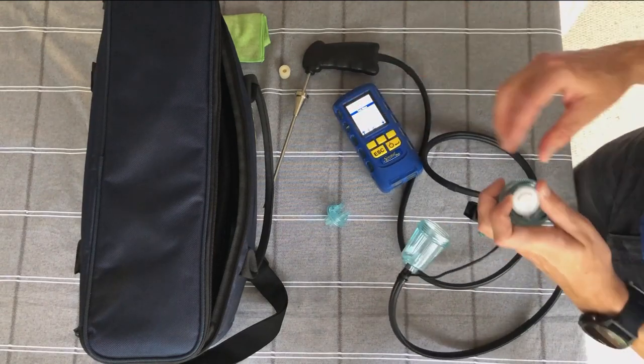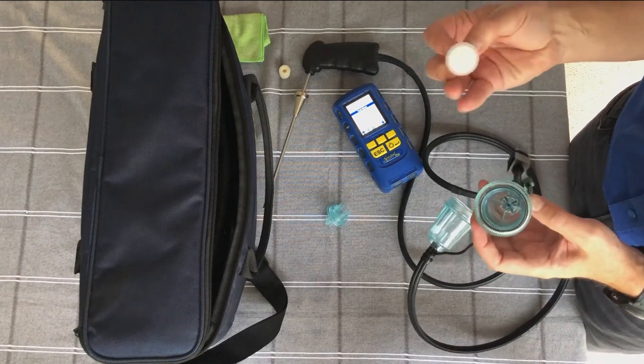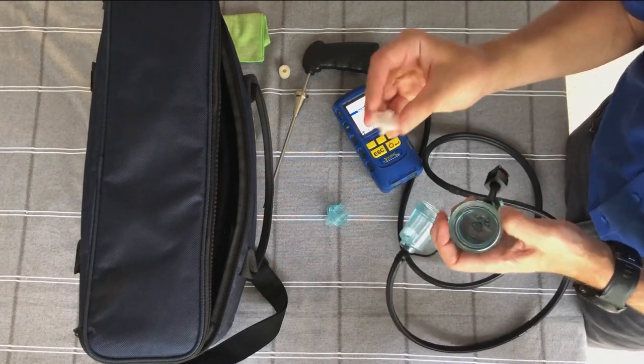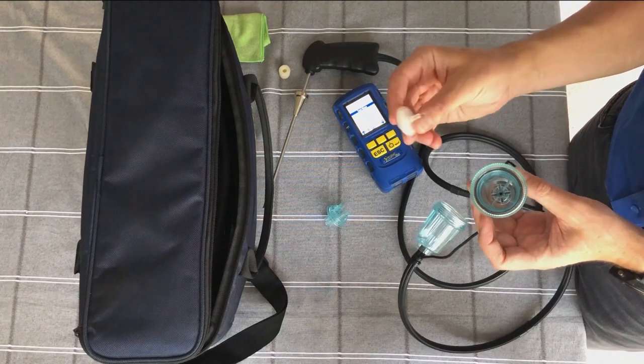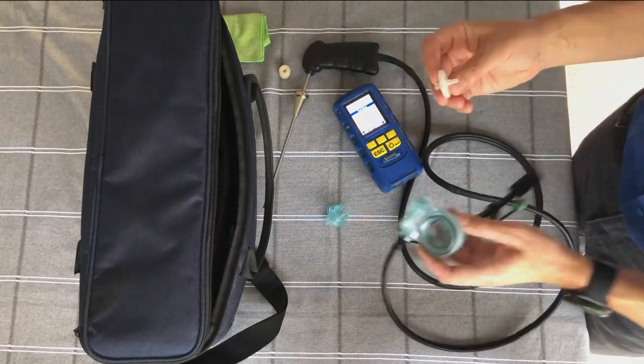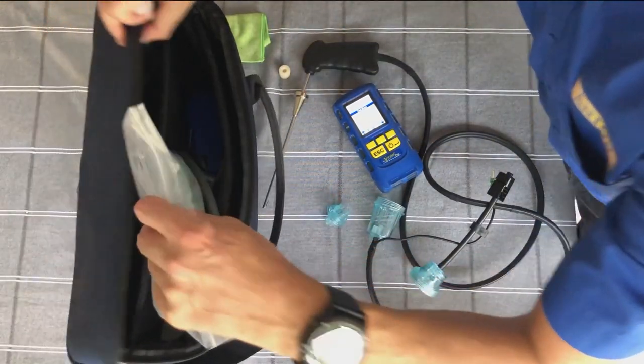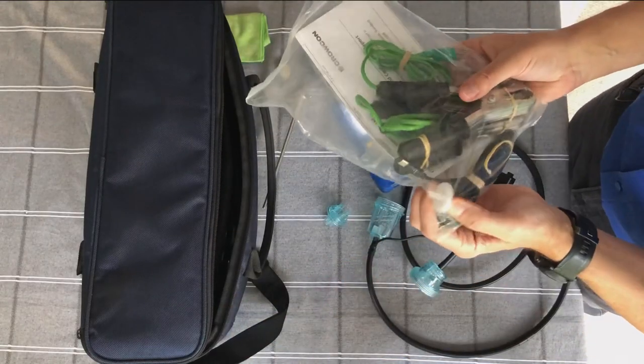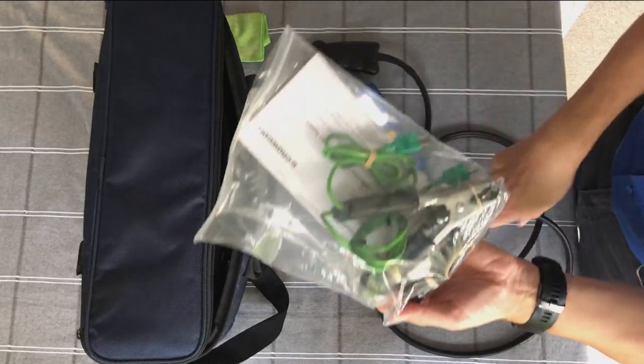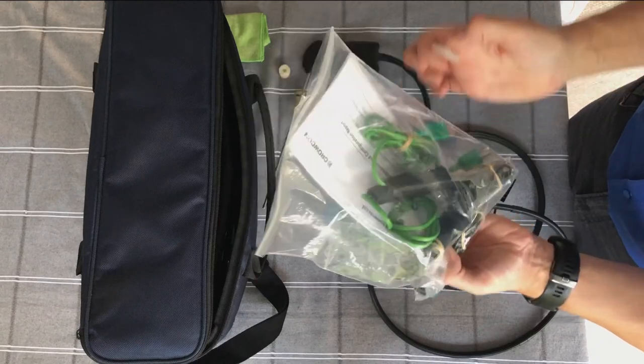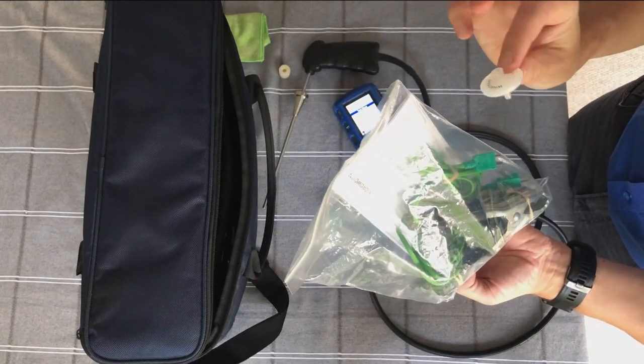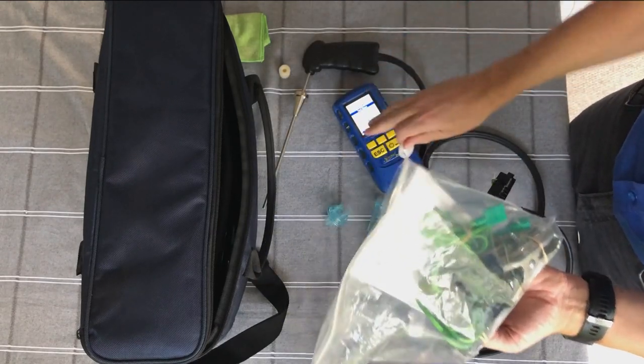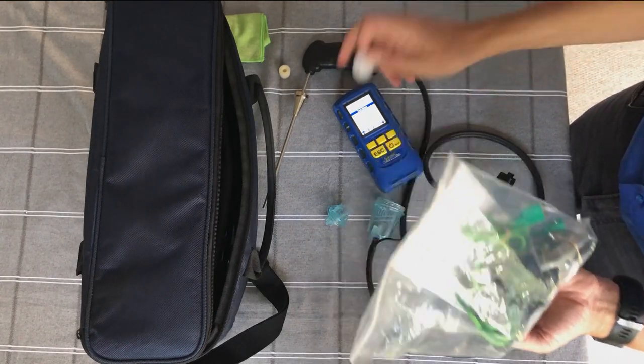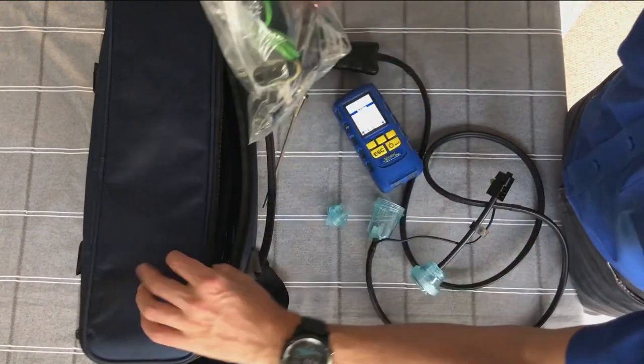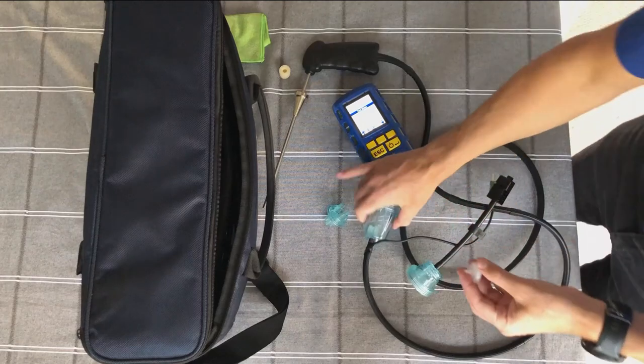So by having this, the idea is you can blow it out. But if you can't blow it out and clear it that way, with all the kits you do get another spare filter. So you can put that one back into the filter trap. Don't throw that one away, it'll just dry out and it'll be usable again, but it's done its job, it's stopped moisture getting into the instrument. Much easier to swap that out than it is to obviously have to send your analyzer away for repair.